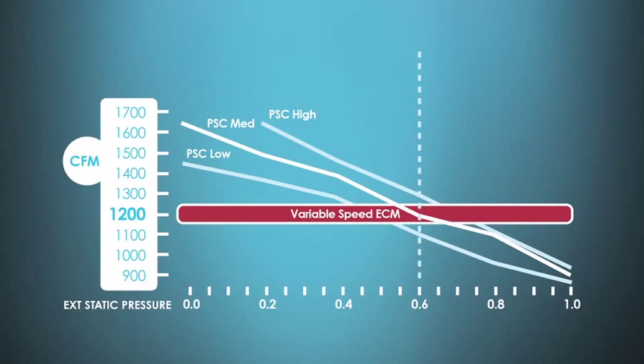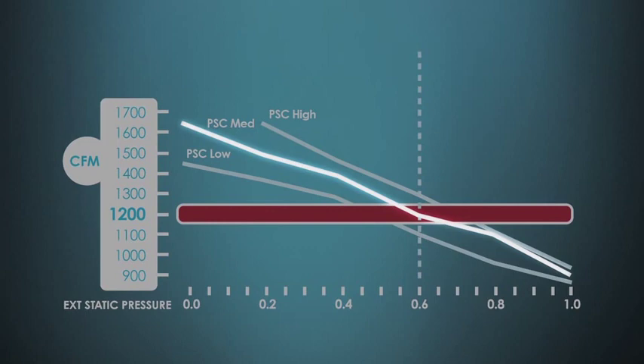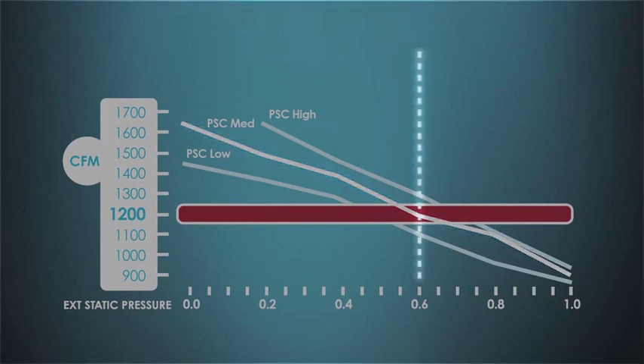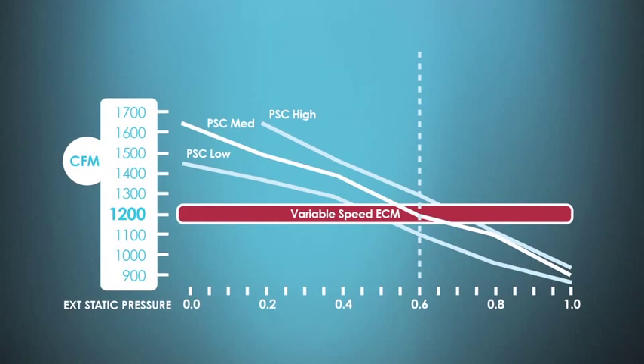A PSC motor doesn't even come close. Looking at the middle line — the medium speed on a PSC motor — we see that the only time it's even close to making 1200 CFM is at 0.6 static, and as external static pressure goes up, airflow continues to go down. Manufacturers rate their equipment for efficiency and capacity according to AHRI at usually around 0.5 or less total external static pressure. So if the PSC motor has to run at higher static pressure to make the same airflow, the system is actually running at under capacity and under efficiency. The variable speed motor actually maintains capacity and efficiency using constant airflow technology.